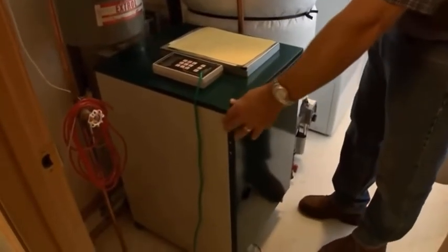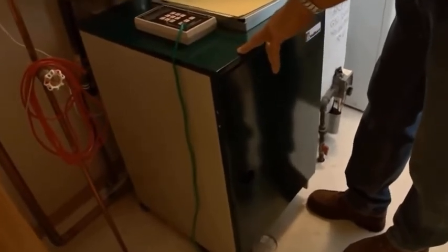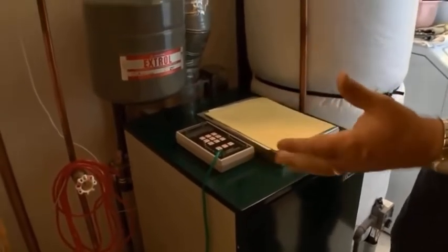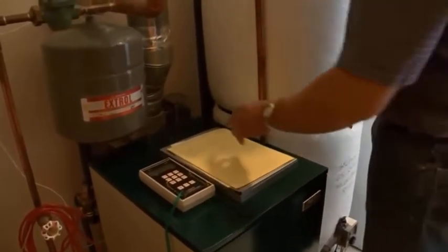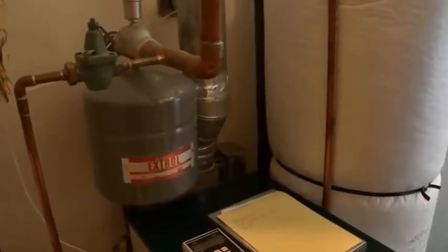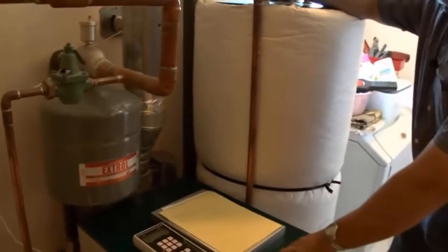What we have here is a Vaillant 80,000 BTU input low pressure water boiler. A couple things I noticed right off the bat without digging into it: the vent damper back in this area right here looks like it's failed and someone has wired it open, so it's not even being used. It's just wired in the open position. The vent damper actually is an efficiency device. It helps increase the efficiency of this boiler.